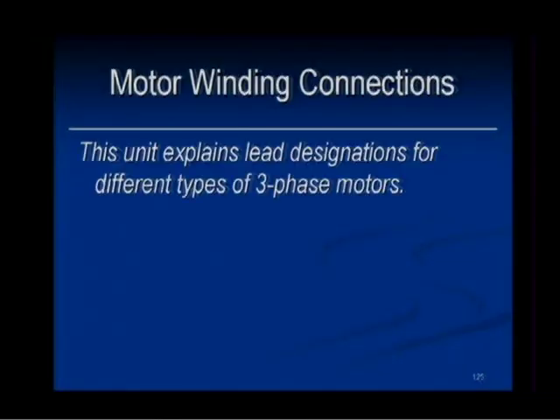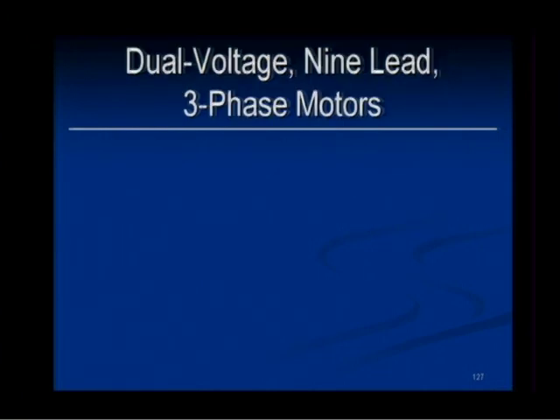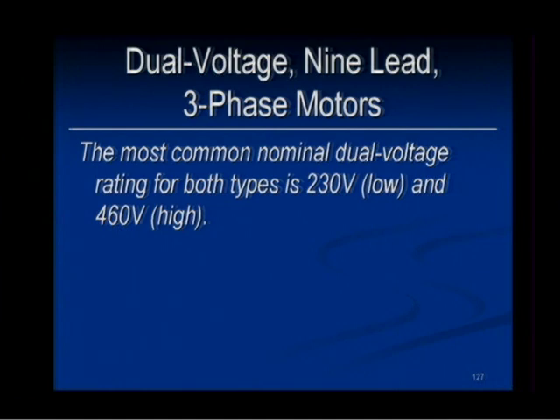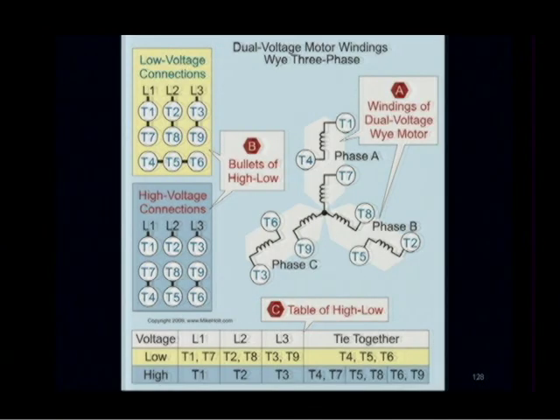Motor winding connections. This section explains lead designations for different types of three-phase motors. All right, we got dual voltage 9-lead three-phase motors. Let's take a look at this one. Most common would be 230 for low voltage and 460 for the higher of the two voltages. All right, let's see what we got here.